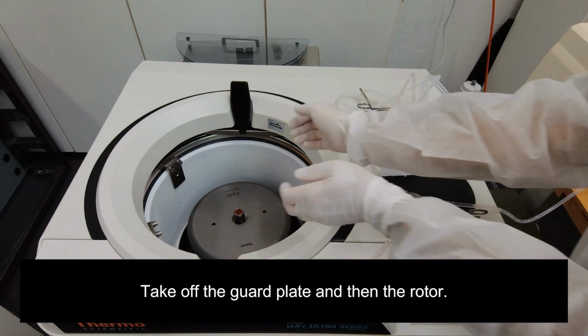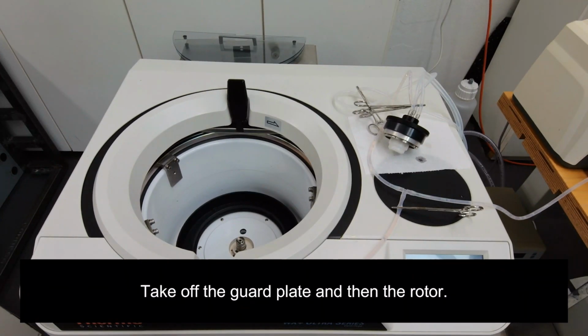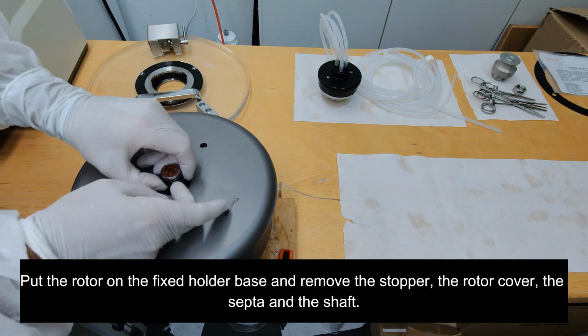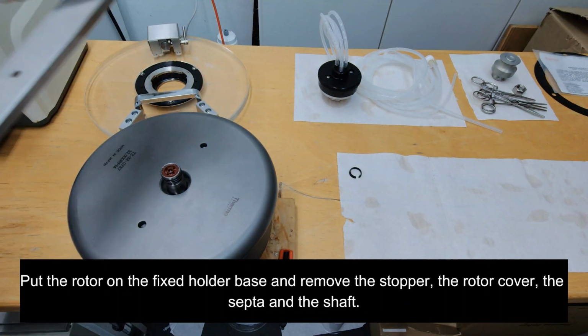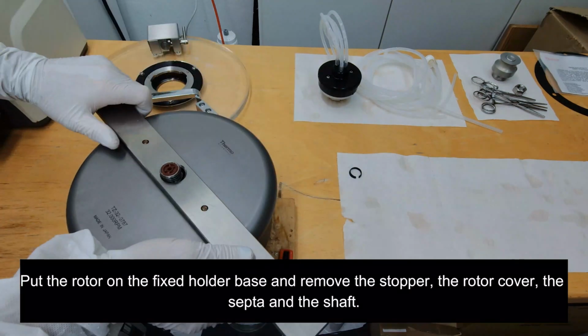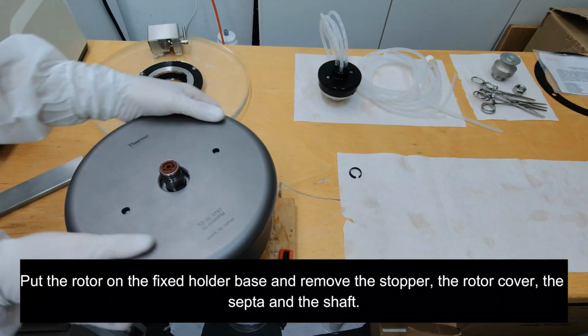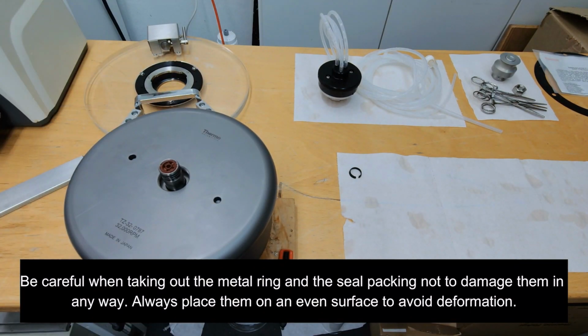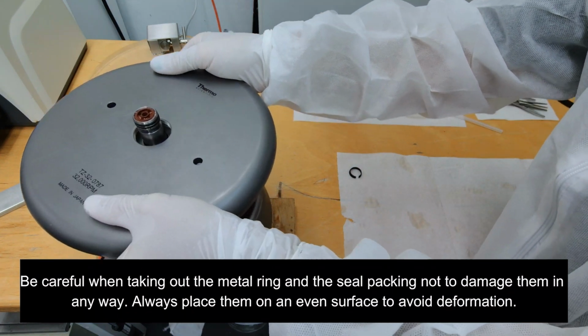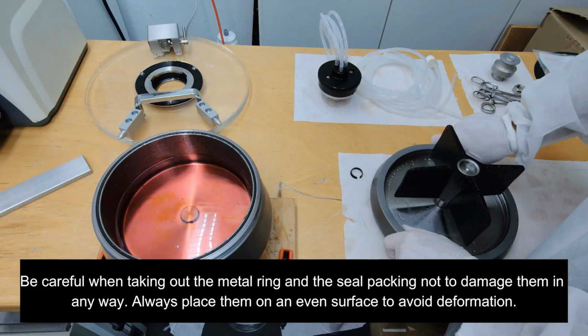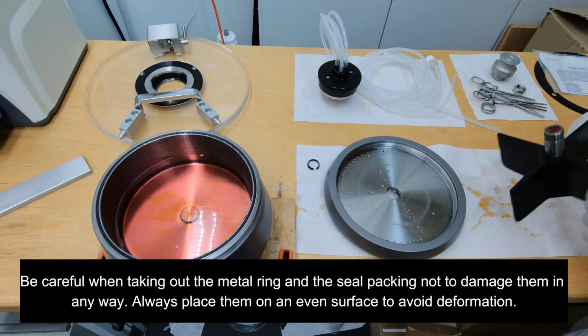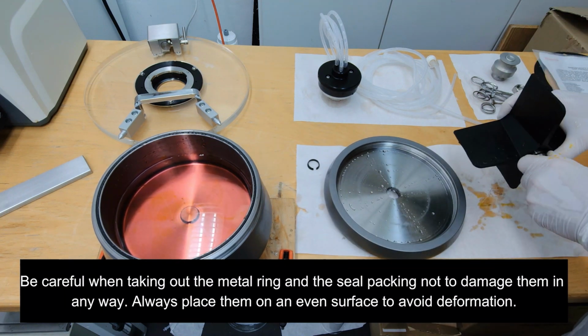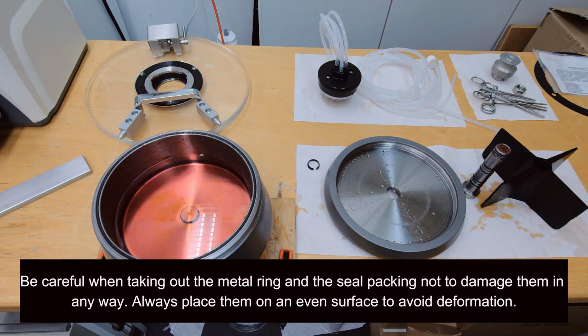Take off the guard plate and then the rotor. Put the rotor on the fixed holder base and remove the stopper, the rotor cover, the septa, and the shaft. Be careful when taking out the metal ring and the seal packing not to damage them in any way. Always place them on an even surface to avoid deformation.